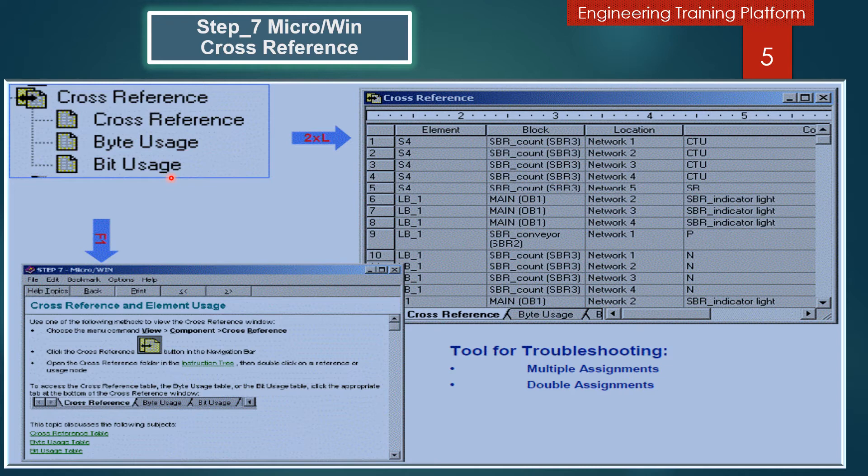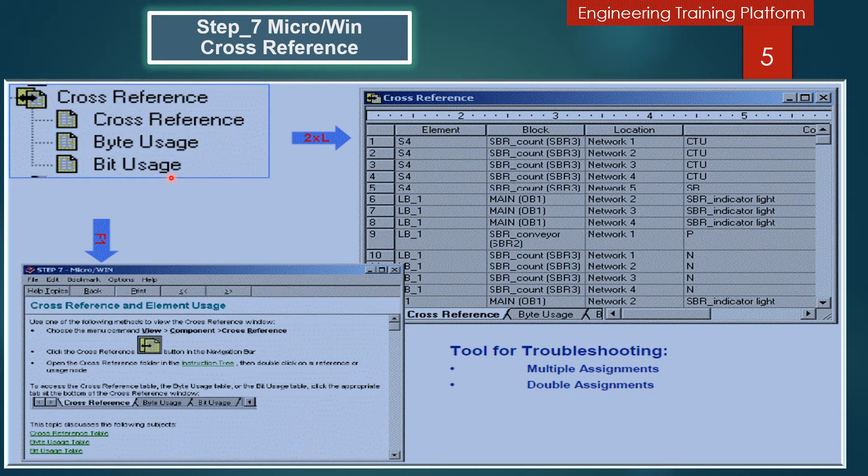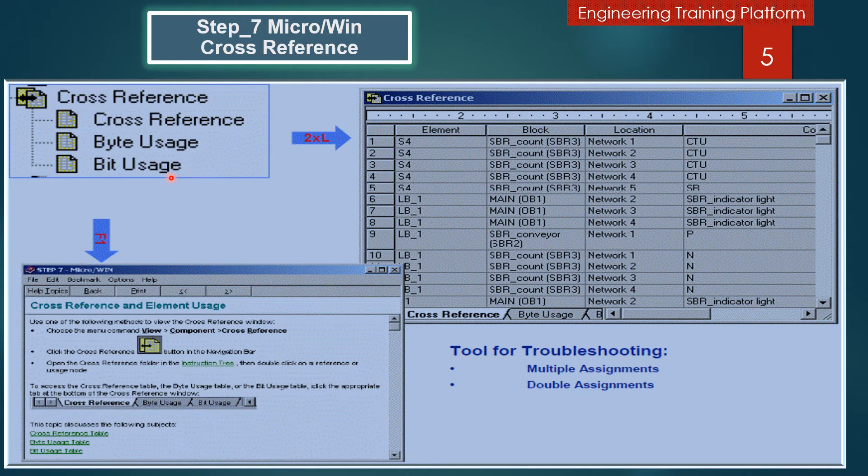The Bit Usage table allows you to see which memory line addresses at the byte level have been used. It also helps you recognize duplicate assignment errors. Now I will define the symbols and their functions. Small 'b' indicates that a bit of memory has been assigned. Capital 'B' indicates that a byte of memory has been assigned. Capital 'W' indicates that a word (16 bits) has been assigned. Capital 'D' indicates that a double word (32 bits) has been assigned. 'X' is used for timers and counters.